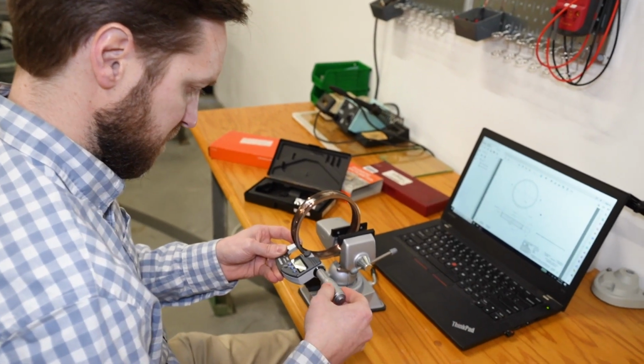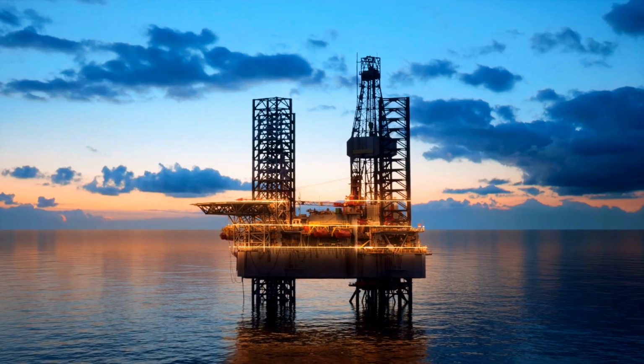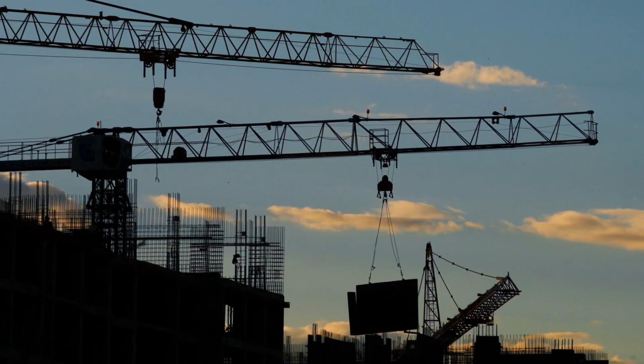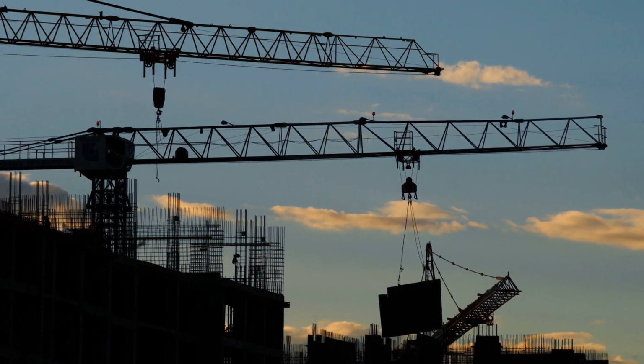A natural extension of strain gauging is to calibrate the parts after the installation is complete. We have a dedicated calibration lab here at our facilities, and we also perform calibrations in the field with the appropriate loading fixtures and reference equipment, which is traceable to NIST.